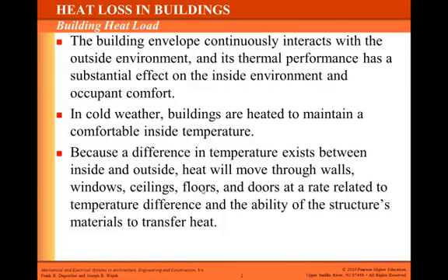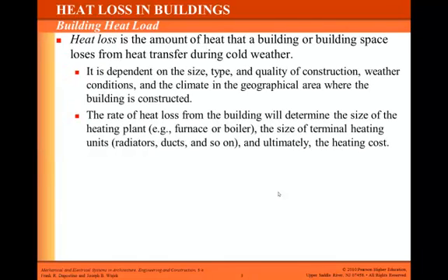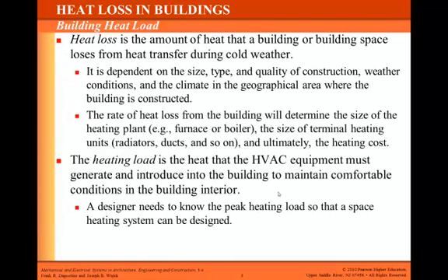So we're particularly concerned about the location of the building and what the outside design temperature is, because it's the difference between these two temperatures that drives the heat loss and heat gain of the building. The heating load will determine the requirement for the furnace or the heat pump for a building. So we will do this procedure of heat loss for each room of a building, and the total sum of all rooms will become the heat loss for the entire building.